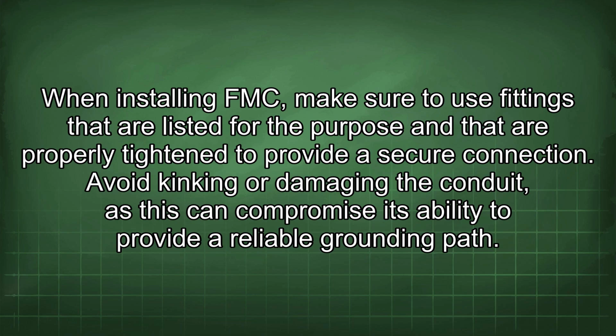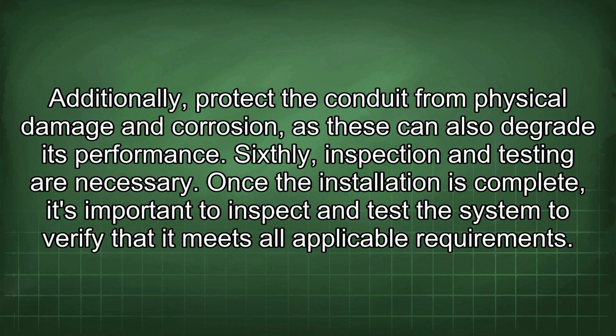provide a secure connection. Avoid kinking or damaging the conduit, as this can compromise its ability to provide a reliable grounding path. Additionally, protect the conduit from physical damage and corrosion, as these can also degrade its performance.